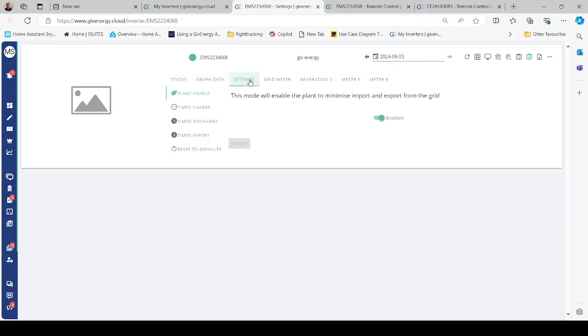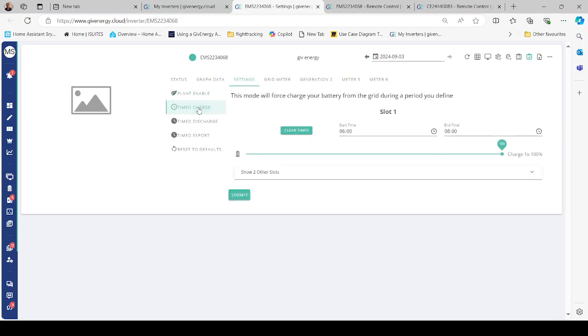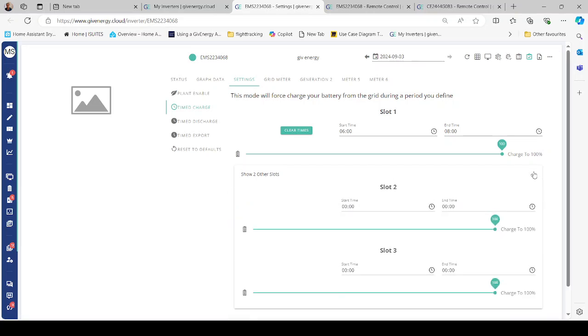Let's look at settings. Settings is where you will enable and disable the EMS, as shown on here. We are enabled at the moment. Set a time charge. If a user tells you his EMS is not charging, just make sure that there is a time charge period in here. You can set 3 time charges up, and on the new version of the portal, you have to click for the other 2 charge slots, slot 2 and slot 3. They will start at 0000 and end at 0000. You cannot do multi-day spanning on a single charge slot.